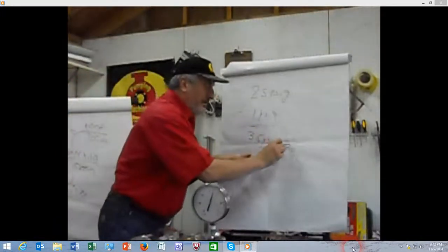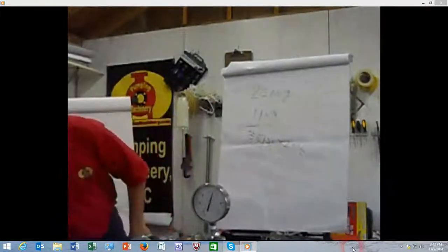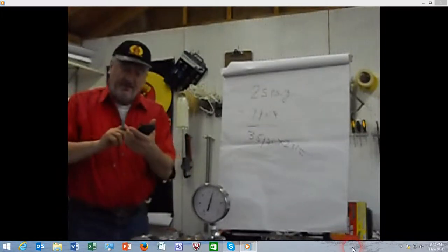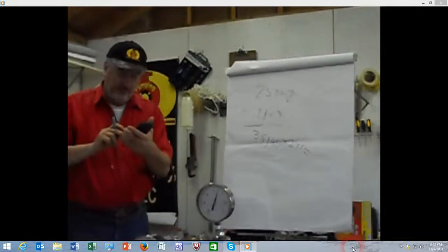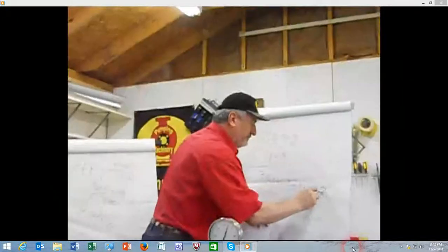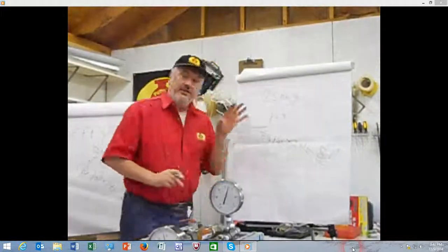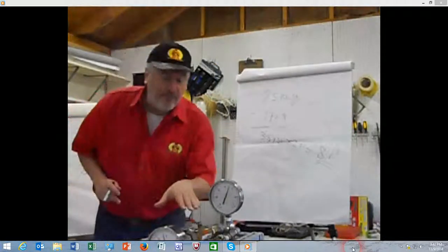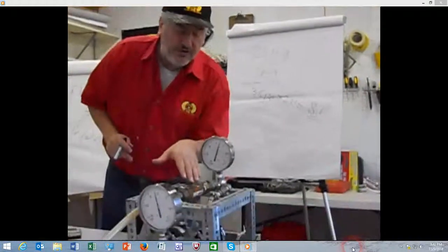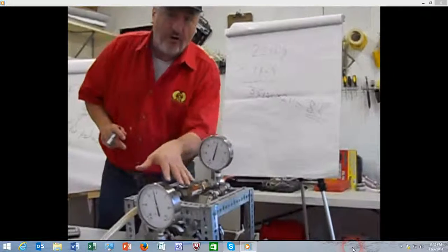Times 2.31. Get it? 8.1 feet. 8.1 feet of head. The flow is 3.2 gallons a minute, as I'm reading it off the flow meter.